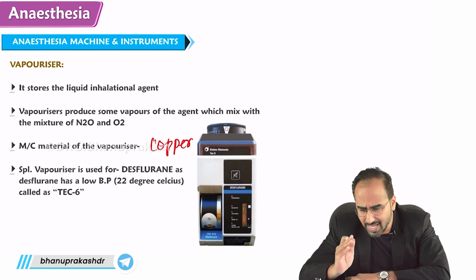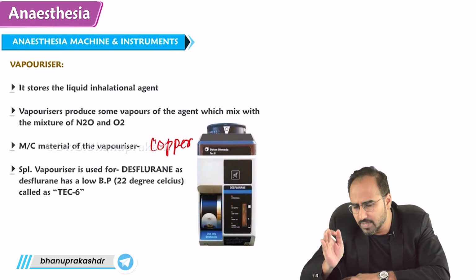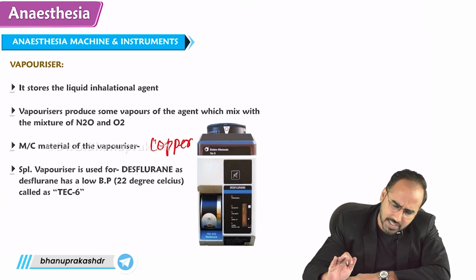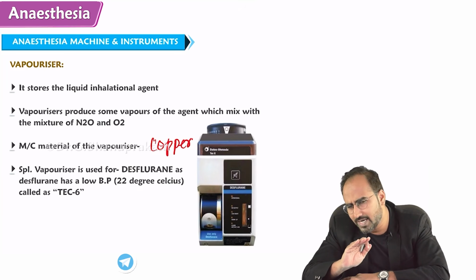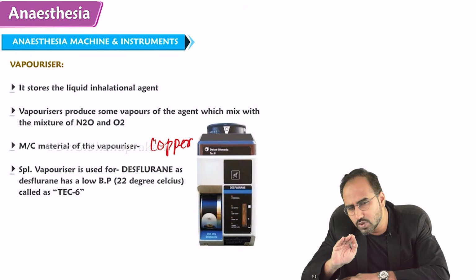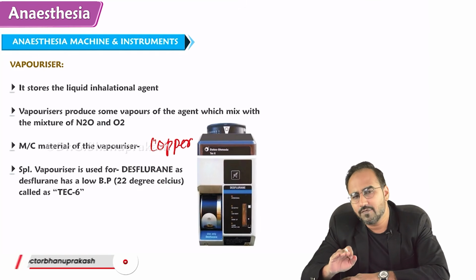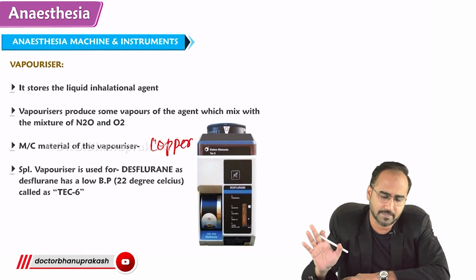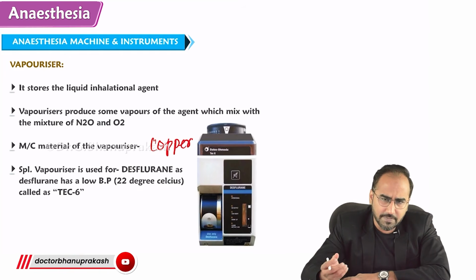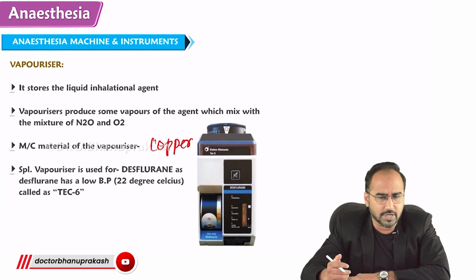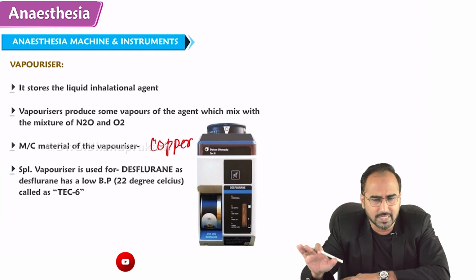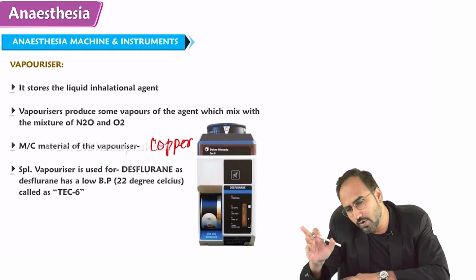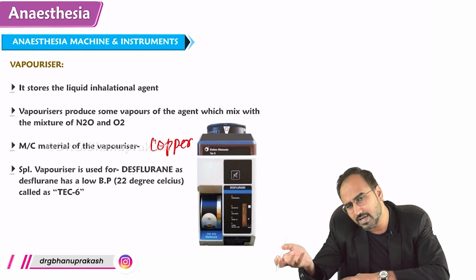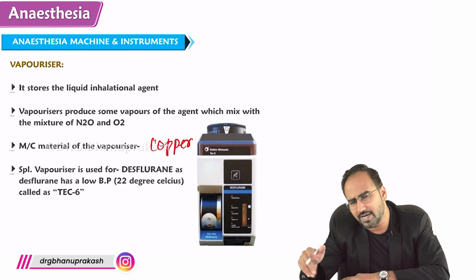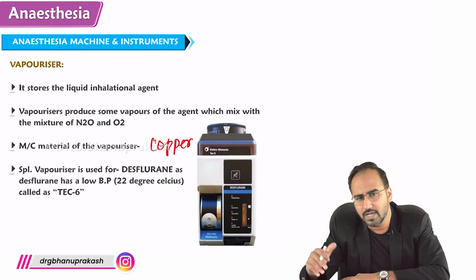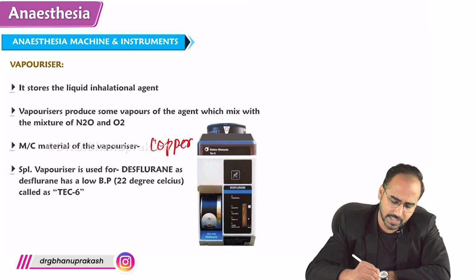Copper. So as you are giving the gases from the cylinder, the gas enters the machine, it goes into the flow meter. From the flow meter, the gas goes to the vaporizer. From the vaporizer, it is given to the patient. Right? So vaporizer produces some vapors mixed with the nitrous and oxygen. So basically you are giving oxygen and nitrous. It goes into the flow meter. From the flow meter, it goes into the vaporizer. It takes the halothane vapor or it might take sevoflurane vapor, and then it will be delivered to the patient.